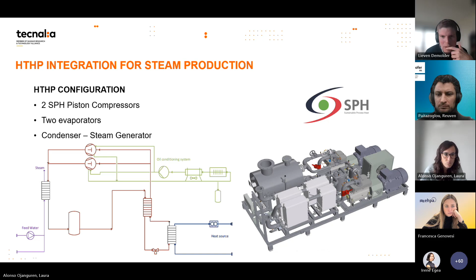Okay, in this slide we can see the basic P&ID or layout of the installation. So the water will be taken from the district heating to some headers, from which it will be transported to the evaporators of the heat pump. We cannot see the evaporators in this view of the heat pump because they are located behind the steam generator, shown in here. Then we have the other inlet of water, which is the feed water, directly to the condenser. Well, first going to the preheater and then to the condenser. And from the condenser, we have the two outlets of steam, which go to a common steam header. And from this steam header, this will come into the process, depending on the process needs, on the heat demands. Okay.